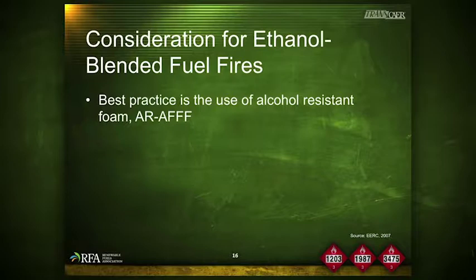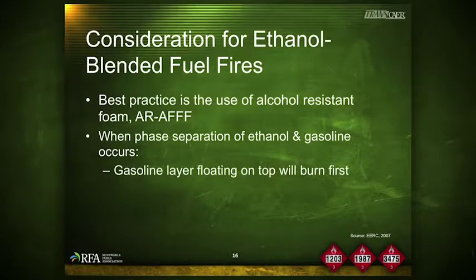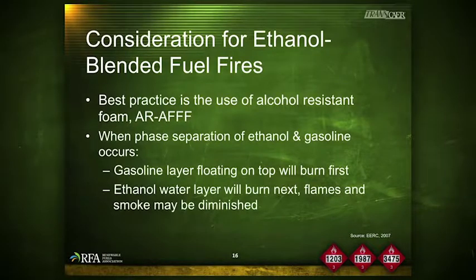Because the AR foam is universally suitable for use on both ethanol and non-ethanol blended fires, the best practice is for emergency responders to keep an AR foam readily available for these incidents. Another noticeable difference of ethanol-blended fuels under fire conditions is that when foam or water has been flowed on the burning product, the gasoline will tend to burn off first, eventually leaving the less volatile ethanol water solution, which may have reduced visible flame or smoke.